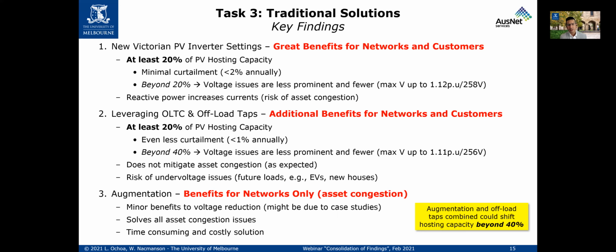Now, leveraging the on-load tap changer at the zone substation and offload tap changers is something DNSPs across Australia are already doing, and that's something good that does bring benefits. If you already have the Victorian settings, it can allow you to go to 20% or even a bit more, and the voltage rise is relatively small, so it's quite good—you can push things really beyond 20%.